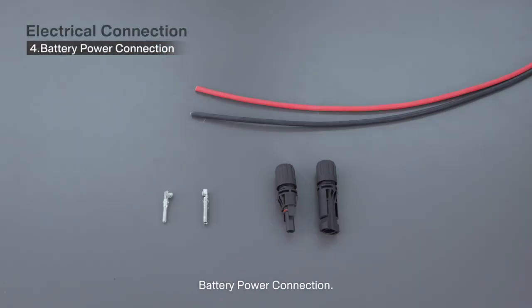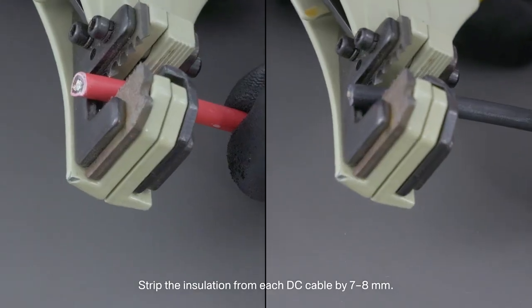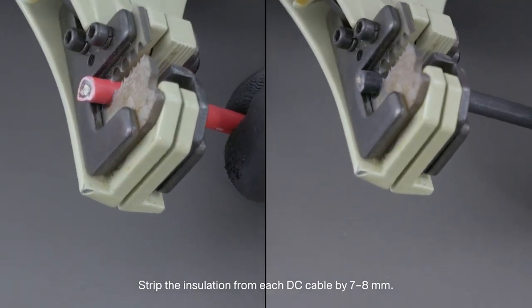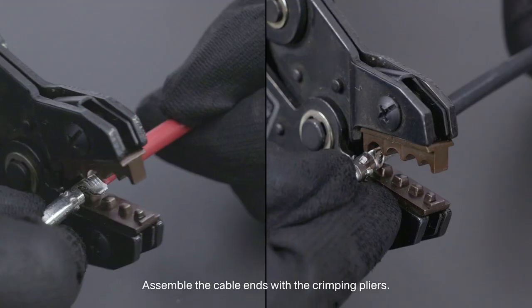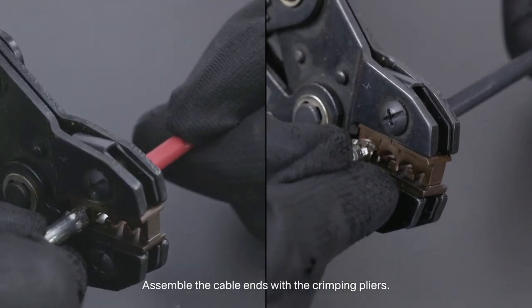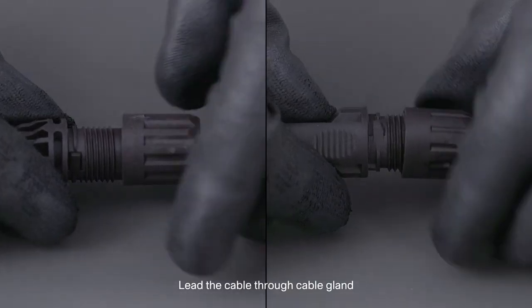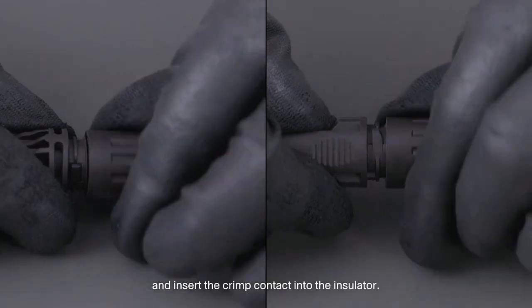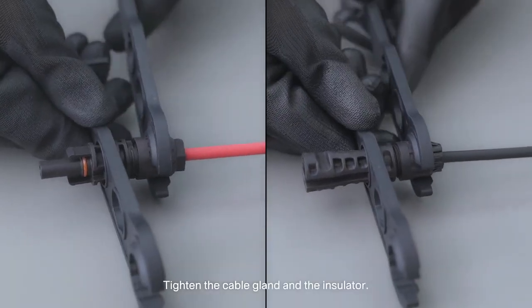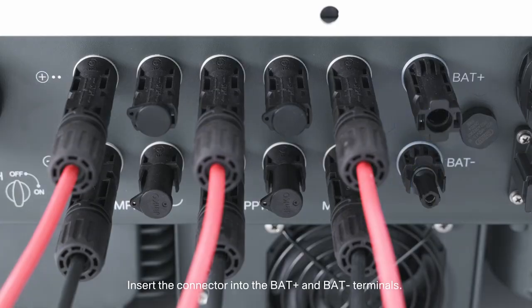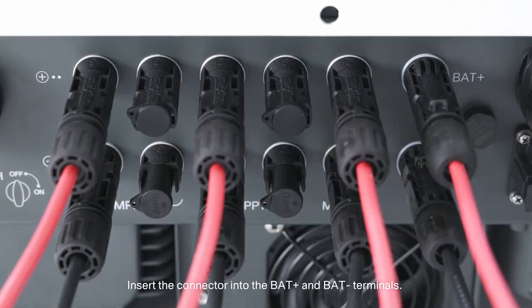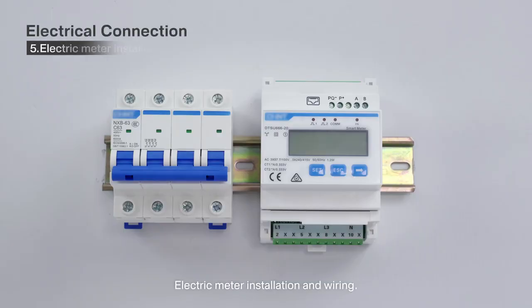4. Battery power connection. Strip the insulation from each DC cable by 7 to 8 mm. Assemble the cable ends with the crimping pliers. Lead the cable through cable gland and insert the crimp contact into the insulator. Tighten the cable gland and the insulator. Insert the connector into the BAT plus and BAT minus terminals. 5. Electric meter installation and wiring.